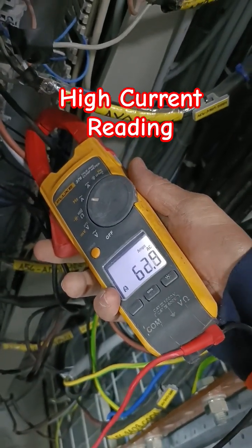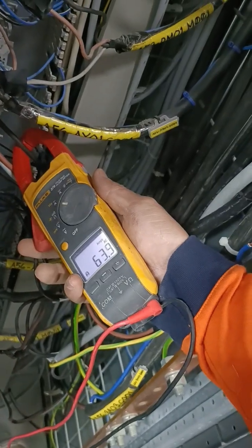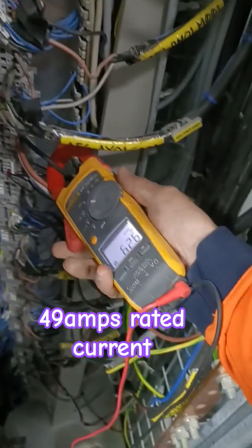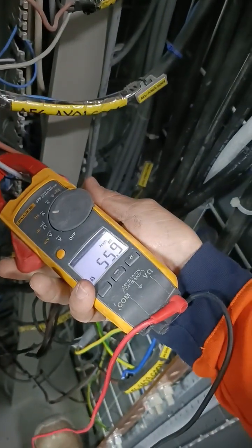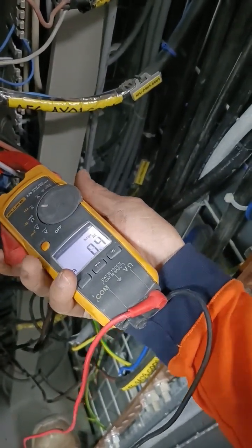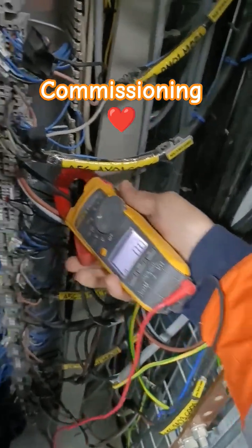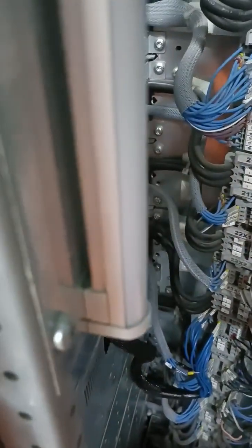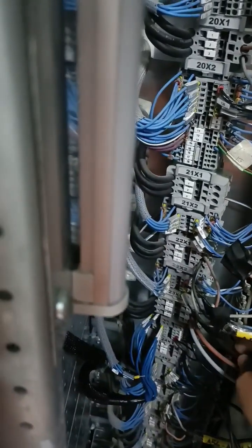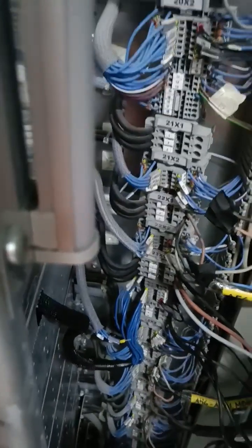What might be the cause of the problem here in our newly installed fan motor? The rated current is just 49 amps, but the actual running current rises to 60 amps on one line and 55 amps on the other. This is a belt drive fan motor and we are testing or commissioning the motor today, but the current reading when I clamp is too high.